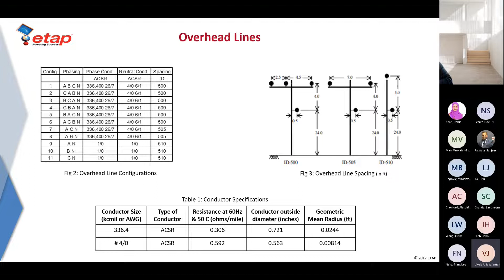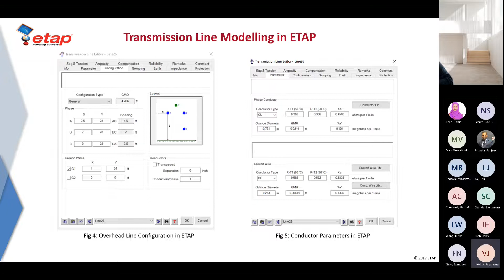So I have phase A at 2.5 and phase B at 7 and phase C at 0. So it's basically CAB. And I have the neutral at 4 and at 24 feet from the ground. So this will help with the GMD, GMR calculations. Whereas the parameter tab that is on the right hand side will help pick the conductor type, material, the resistance. These two settings are pretty much excellent at modeling the transmission line pretty accurately within the system.